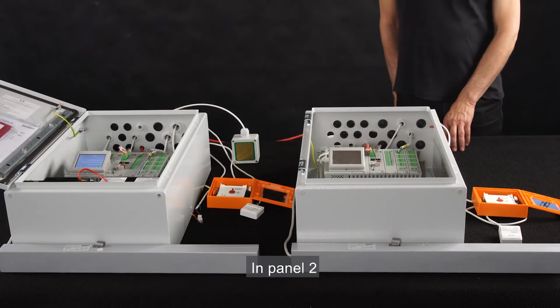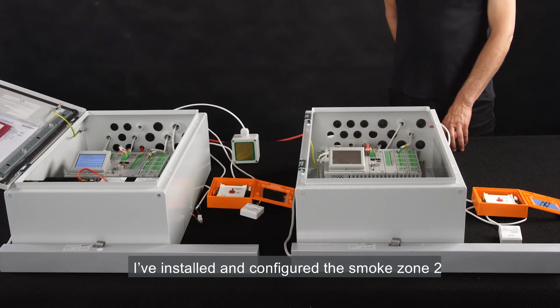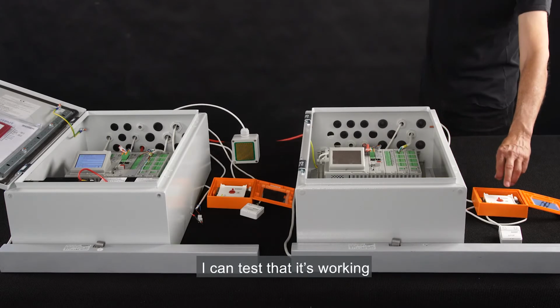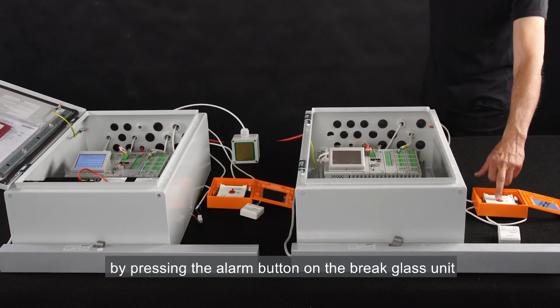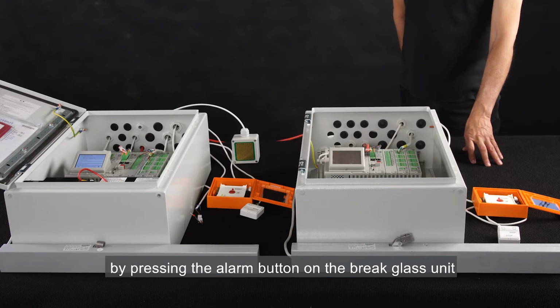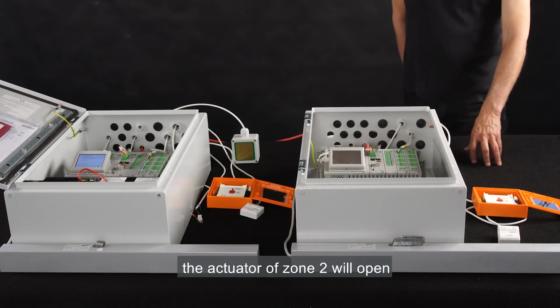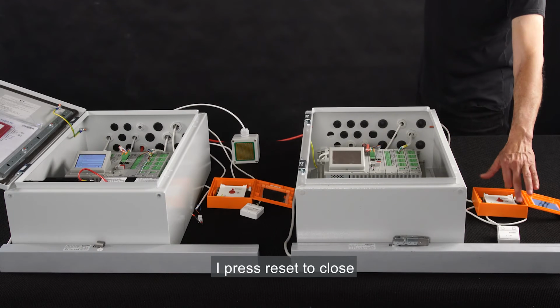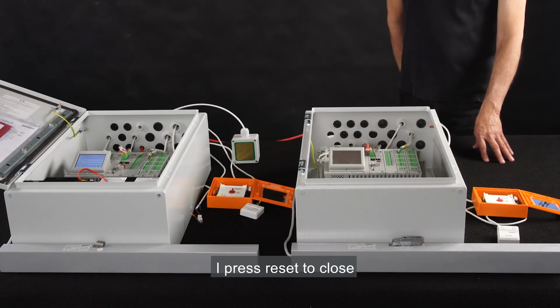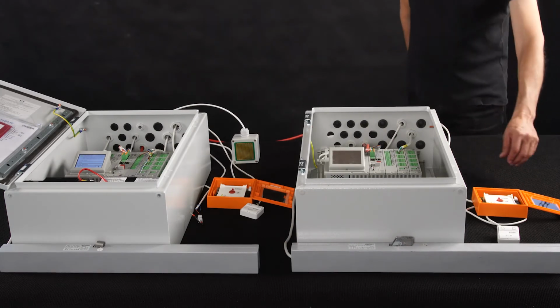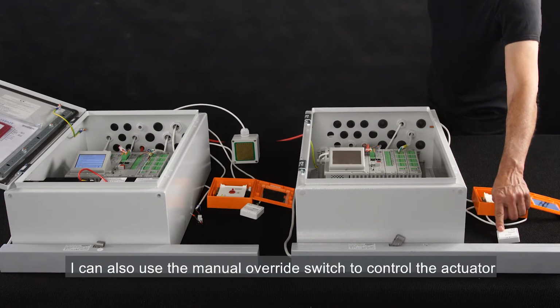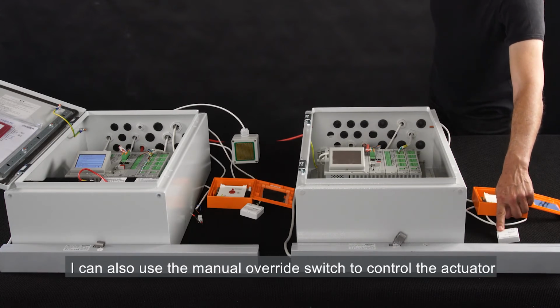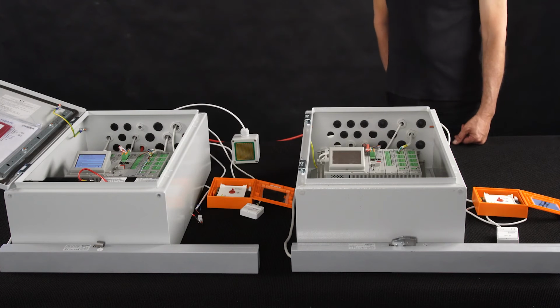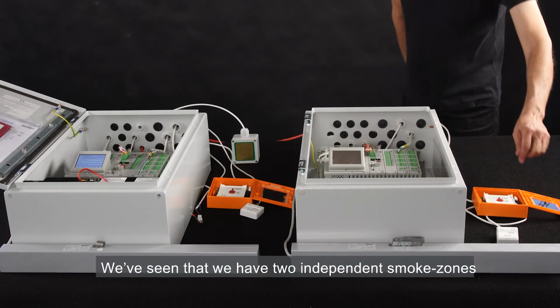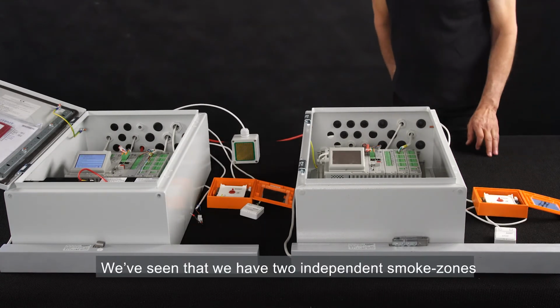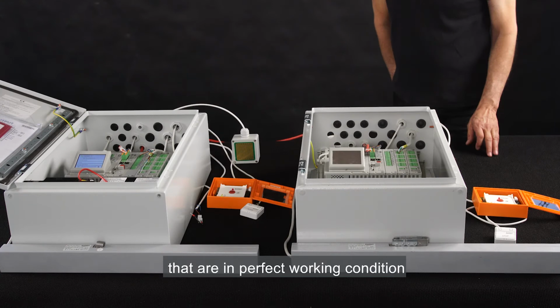In panel 2, I've installed and configured the smoke zone 2. I can test that it's working by pressing the alarm button on the break glass unit. The actuator of zone 2 will open. I press reset to close. I can also use the manual override switch to control the actuator. We've seen that we have two independent smoke zones that are in perfect working condition.